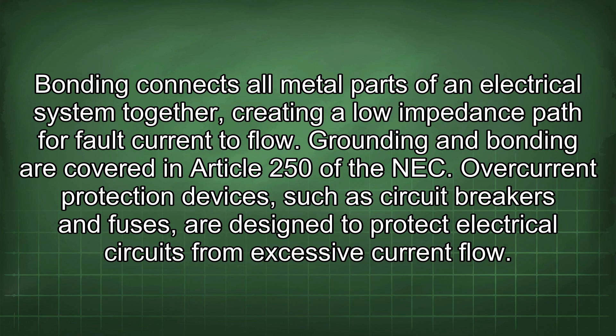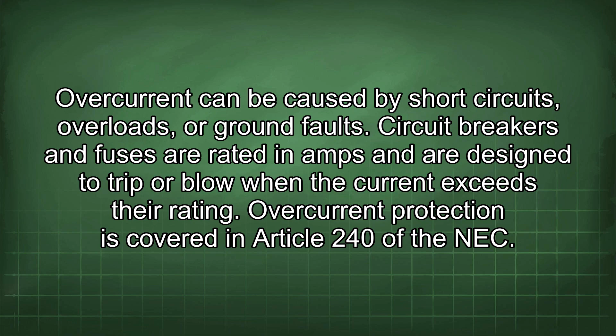Overcurrent protection devices, such as circuit breakers and fuses, are designed to protect electrical circuits from excessive current flow. Overcurrent can be caused by short circuits, overloads, or ground faults. Circuit breakers and fuses are rated in amps and are designed to trip or blow when the current exceeds their rating. Overcurrent protection is covered in Article 240 of the NEC.